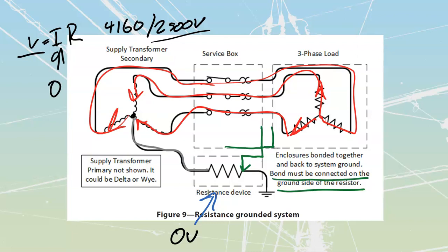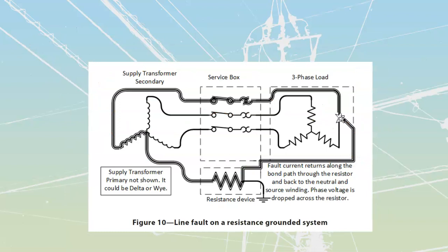Let's look at these systems under a fault over here. Under a fault, which we've identified as being this point right over there, we are going to have connection over to our bonded path. So what we will have now is current delivered over here by my A phase, traveling through here, up to here. Now, the bulk of my current is still going to go through the load back to its transformer like that. But the fault current itself, there's going to be some that travels along here. It goes along the bond path—remember how we have the bond path right over there?—into here, where it has to travel through that resistor and back up to my actual phase over there, the neutral on this thing.